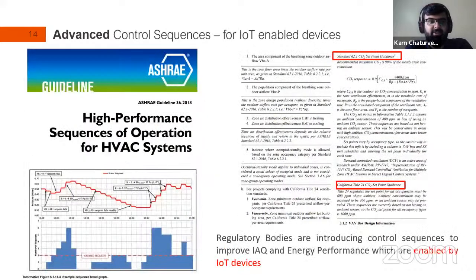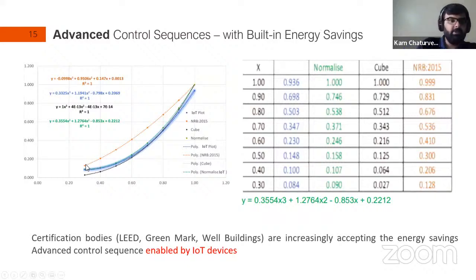This IoT BMS applies a version of control sequence similar to ASHRAE 36. What was observed was that the energy consumption of the NRB 2015 was actually quite high compared to an IoT BMS with GPC 36 control sequences. This orange line represents the VAV performance of very sustainable buildings that have gotten a Green Mark rating from Building Controls Authority Singapore, not normal buildings. So compared to those top of the line buildings, there is still room to save energy using IoT BMS.